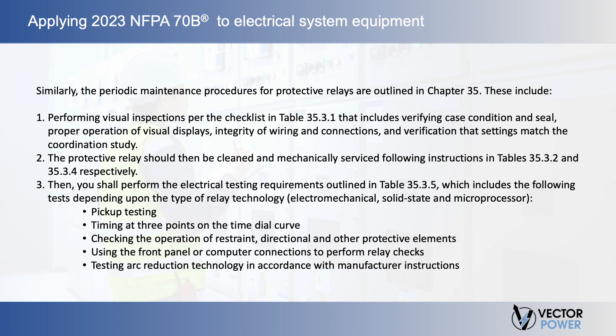These maintenance practices are critical because they directly impact the accuracy of arc flash risk assessment. If a protective device is not properly lubricated or mechanically functioning, operating time can be delayed. This leads to higher incident energy levels than originally calculated in the analysis and can potentially put downstream workers and equipment at risk.